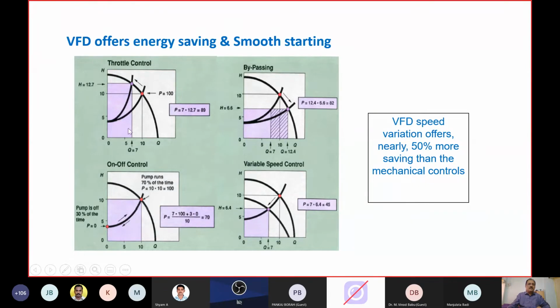If you throttle in order to optimize your flow from 10 to 5 or 10 to 7, let's say, what will happen? The pressure will increase. Throttling will lead to pressure increase. The performance curve has shifted now, yet there is a power saving available, and that is up to about 11%. When you reduce the flow rate, even though the pressure increases, the product of Q into P will give rise to a reduction in power from 100 to 89, which is 11% saving.